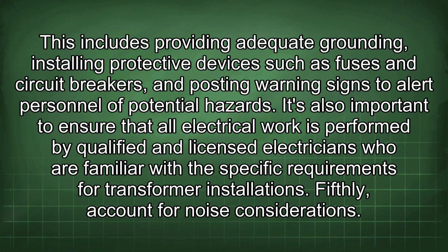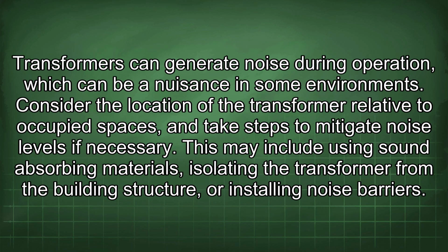Fifthly, account for noise considerations. Transformers can generate noise during operation, which can be a nuisance in some environments. Consider the location of the transformer relative to occupied spaces, and take steps to mitigate noise levels if necessary. This may include using sound-absorbing materials, isolating the transformer from the building structure, or installing noise barriers.